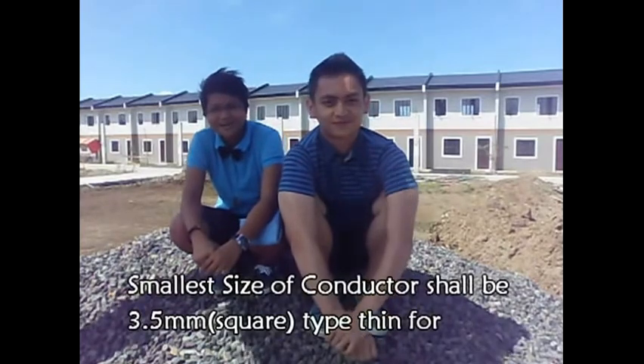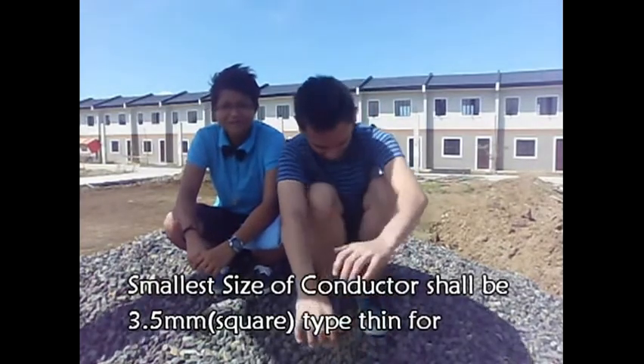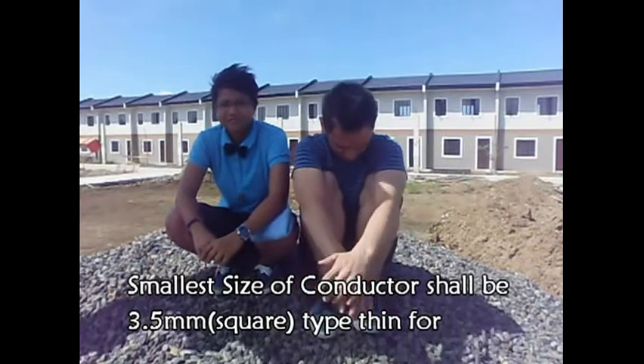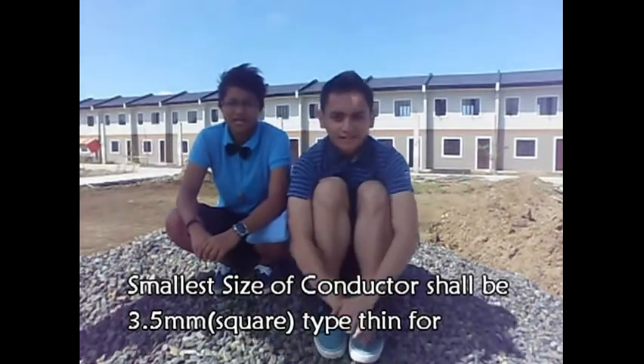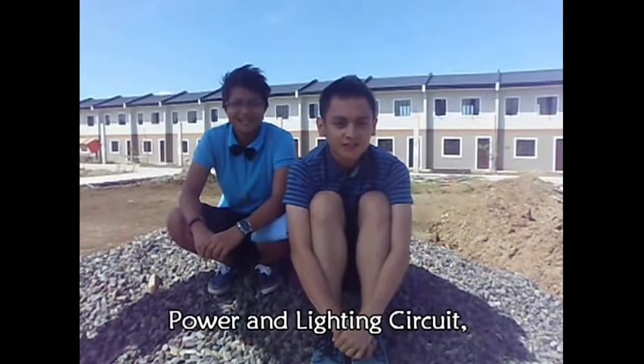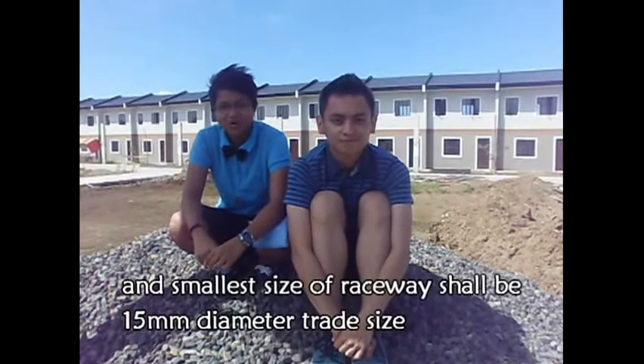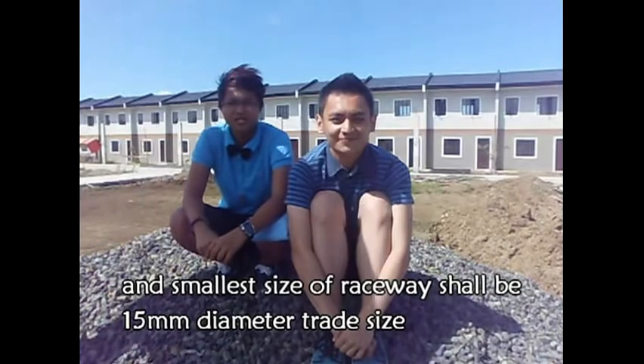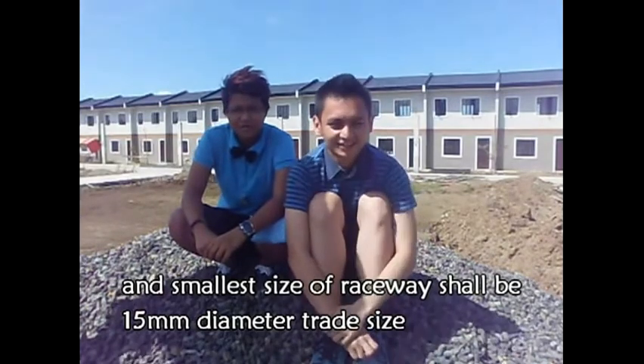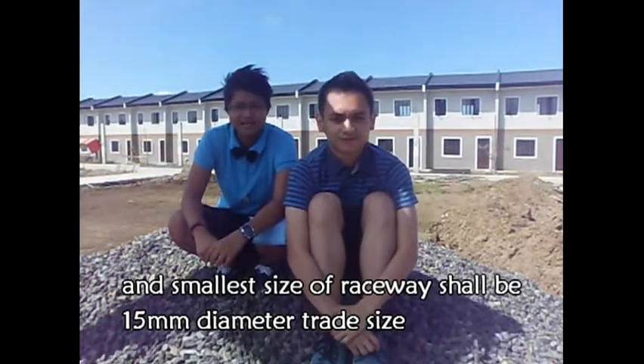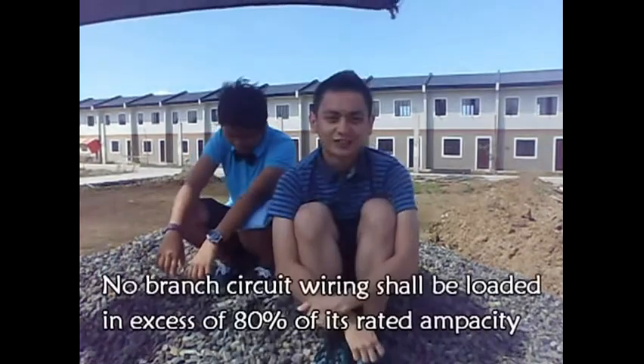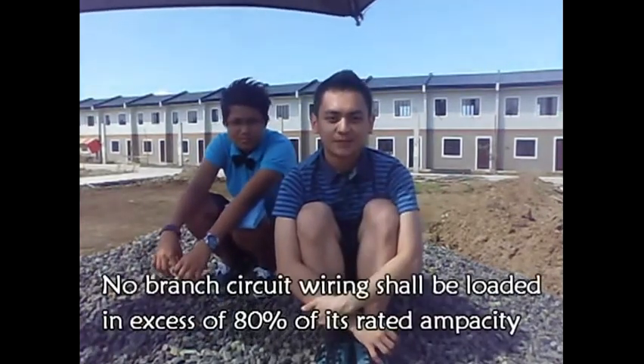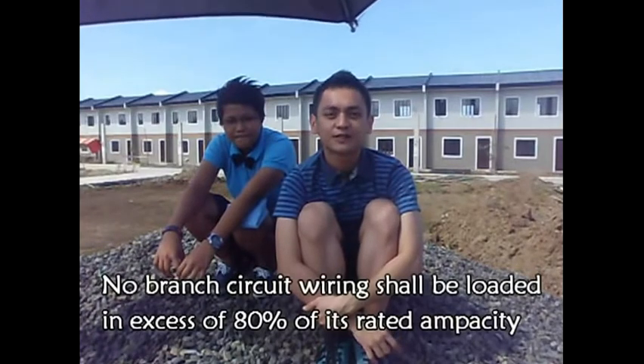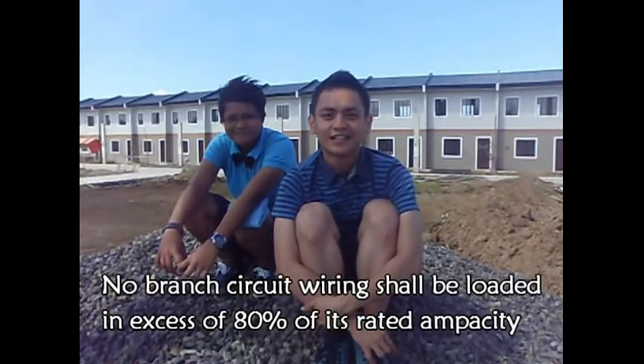Smallest size of conductor shall be 3.5 millimeter squared, type THW for power and lighting circuit. And smallest size of raceway shall be 15 millimeter, conduit size. Number 4. No branch circuit wiring shall be loaded in excess of 80% of its rated ampacity.